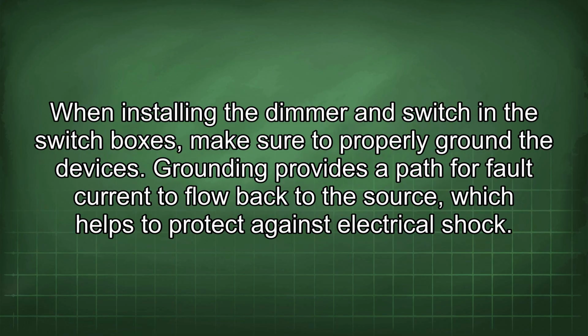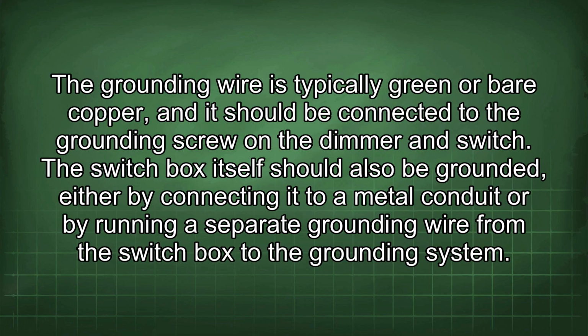When installing the dimmer and switch in the switch boxes, make sure to properly ground the devices. Grounding provides a path for fault current to flow back to the source, which helps to protect against electrical shock. The grounding wire is typically green or bare copper, and it should be connected to the grounding screw on the dimmer and switch. The switch box itself should also be grounded, either by connecting it to a metal conduit or by running a separate grounding wire from the switch box to the grounding system.